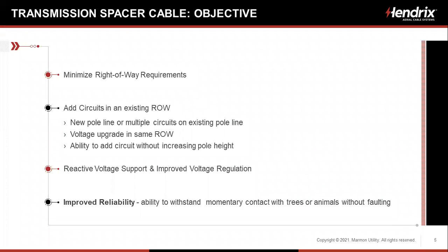We might want to have a voltage upgrade in the same right-of-way: take a 25 kV right-of-way, replace the poles, put in 5-10 feet taller poles, and put a 69 kV on that same pole line. And have the ability to add circuits without increasing pole height. And we'll take a look at this a little bit later.